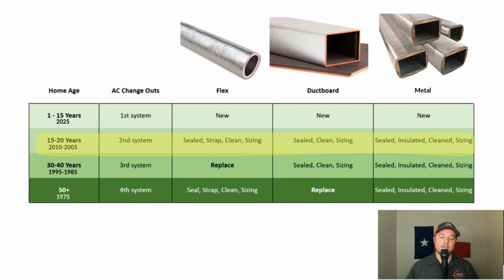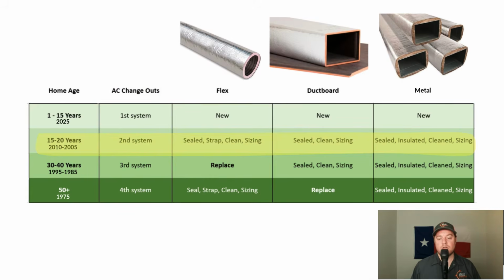A lot of times, as a house gets older and older, it starts to lose efficiency. It's not quite sealed as well as it used to be when it was brand new. The insulation is starting to collapse down a little bit, and the heat loads might call for a little bit bigger of a system. So definitely make sure that the sizing is correct so you don't end up damaging the new system that you're about to buy. Or sometimes in the construction of the home, we'll see some contractors cut corners in order to save a few bucks and install undersized ductwork.